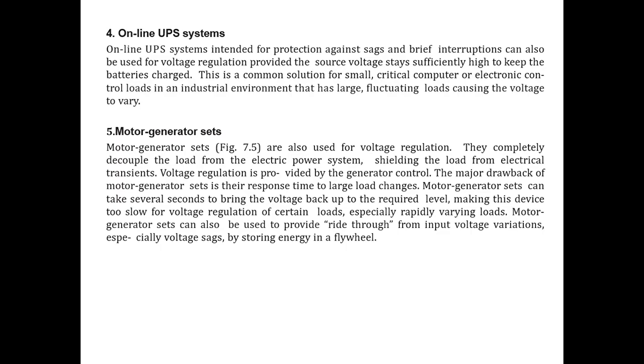Now we are going to discuss the online UPS system, that is, the uninterruptible power supply. An online UPS system intended for protection against sag and brief interruptions can be used for voltage regulation, provided the source voltage stays sufficiently high to keep the batteries charged. This is the common solution for small critical computer or electronic control loads in an industrial environment that has large fluctuating loads causing the voltage to vary.